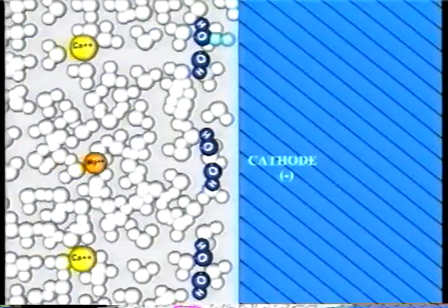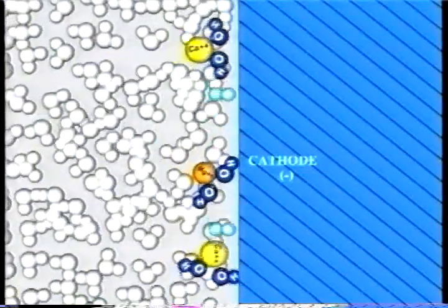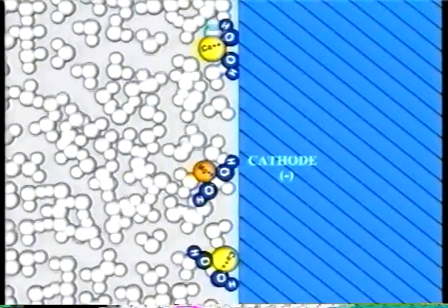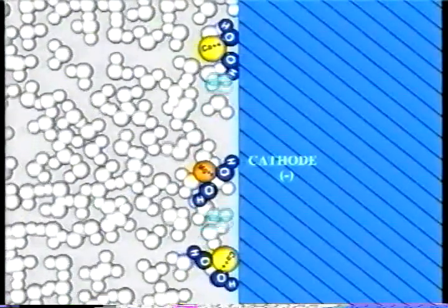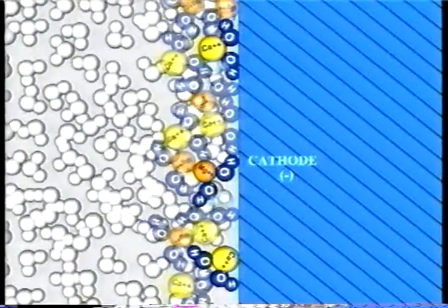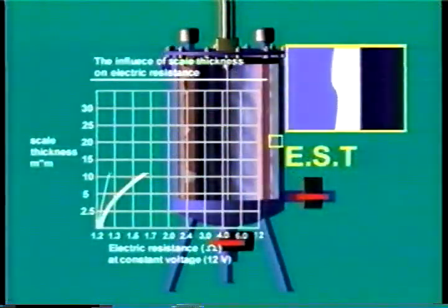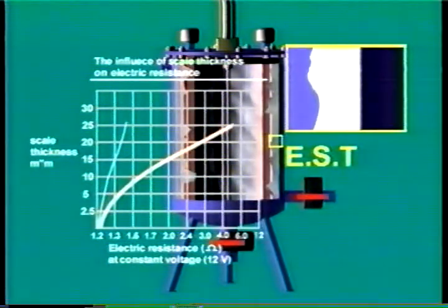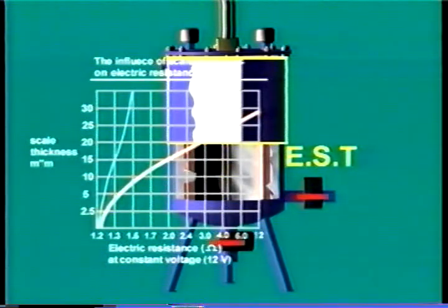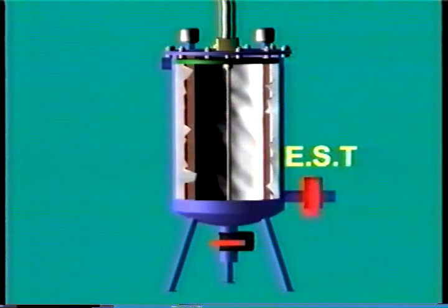The rising accumulation of the various carbonates on the chamber walls causes a rise in the electrical resistance and impedes the electrical current. To prevent this and to maintain the efficiency of the electrolysis process, the EST+L system continuously measures and monitors the electrical resistance in order to determine the appropriate time for wiping off the scale from the chamber walls. The cycle of wiping the scale off the chamber walls begins by first closing the water inlet valve and then opening the drainage valve at the bottom of the chamber.